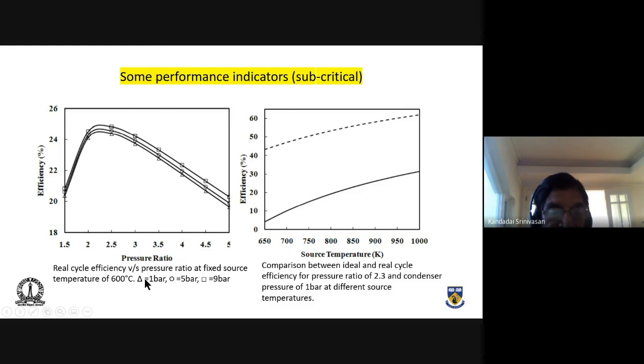Once the pressure ratio is there, you can see that at low operating pressures there is not much of a difference. Of course, there is a very little increase in the efficiency as you keep increasing the pressure. The triangles are the 1 bar, 5 bar, and 9 bar. As you go to higher and higher pressures, the efficiency goes up. The low pressure goes up because of the pressure ratio, and the upper stage pressure also goes up. If it's 9 bar, the optimum comes at about 2.25, so 9 times 2.25, a little over about 20 bar, will be the upper stage pressure. But what efficiency are we talking about? Not more than about 25%.